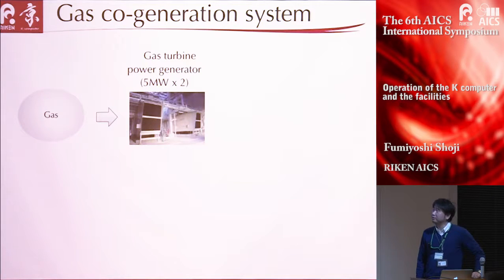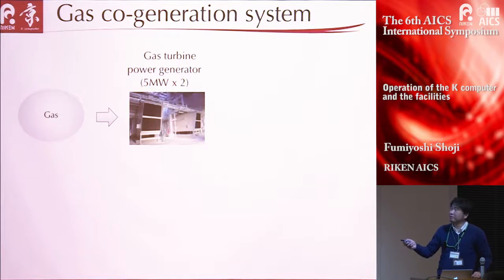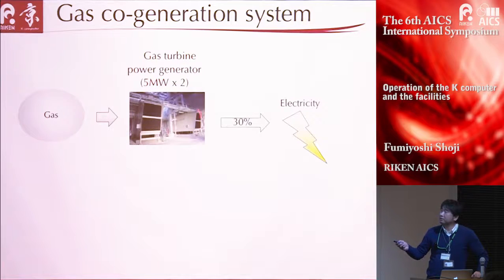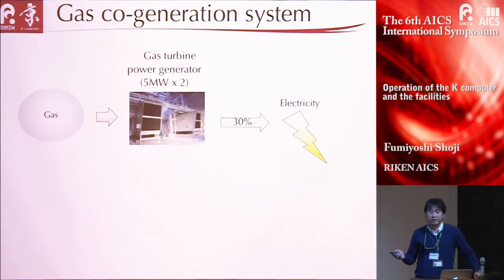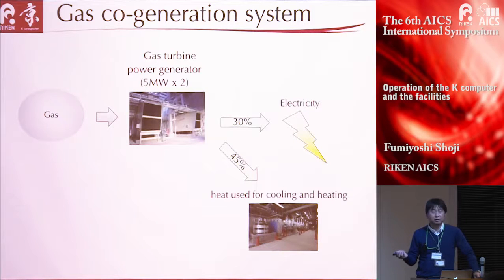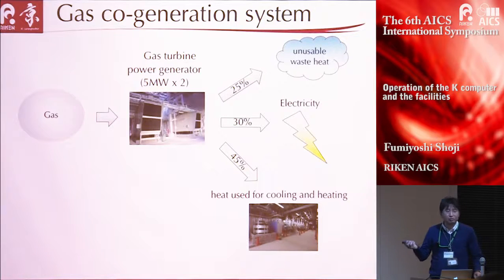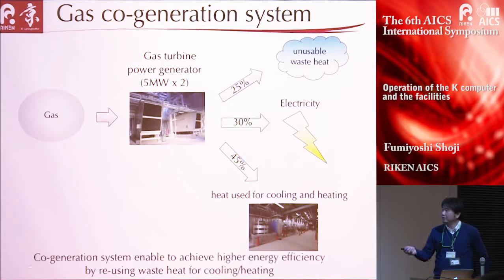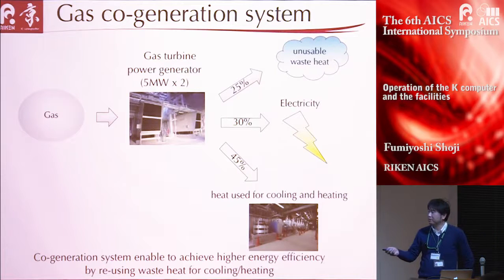This is a brief introduction of the gas cogeneration system. We have two gas turbine power generators. The generators produce electricity, but only 30% of the potential energy of gas can be converted to electricity. However, 45% of the energy can be used for cooling and heating by this system. The remaining energy becomes unusable wasted heat. This system achieves higher energy efficiency by reusing wasted heat for cooling and heating.